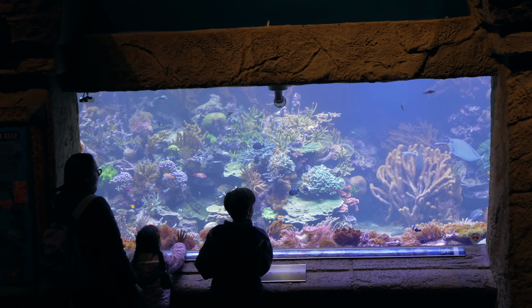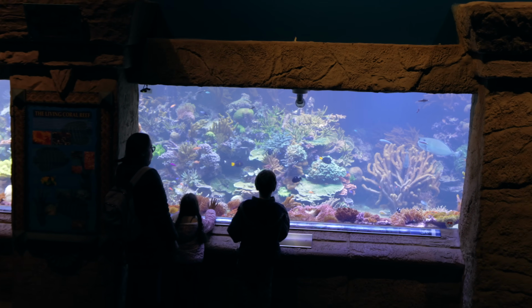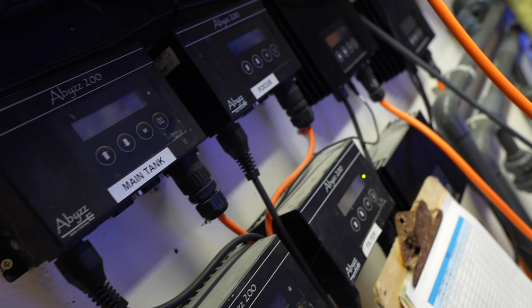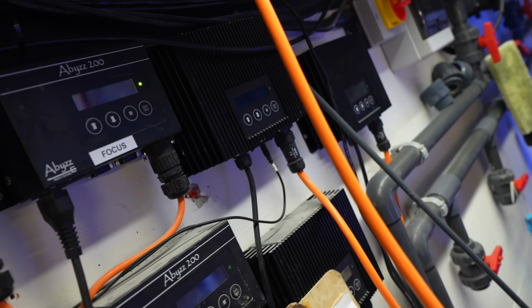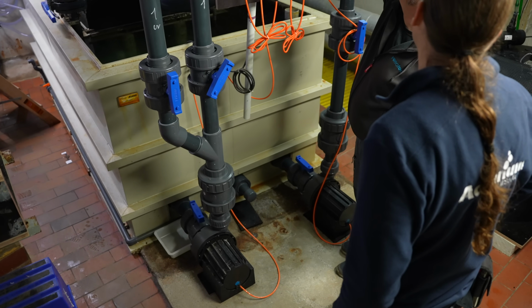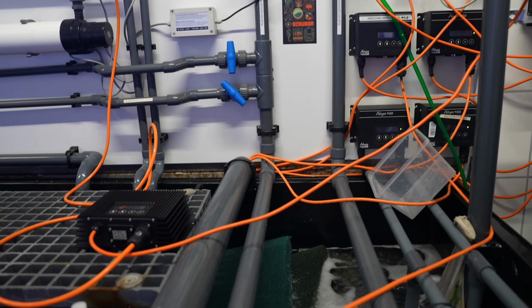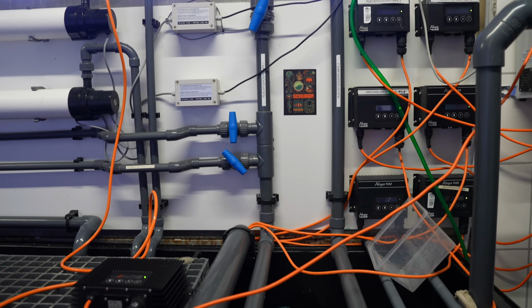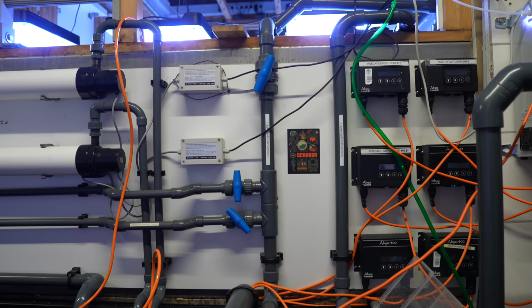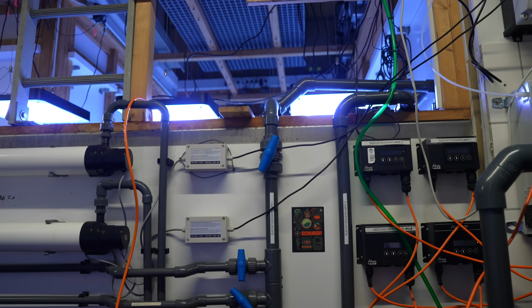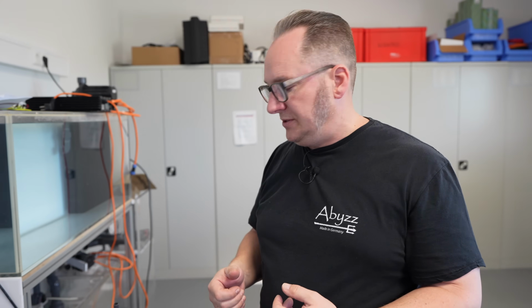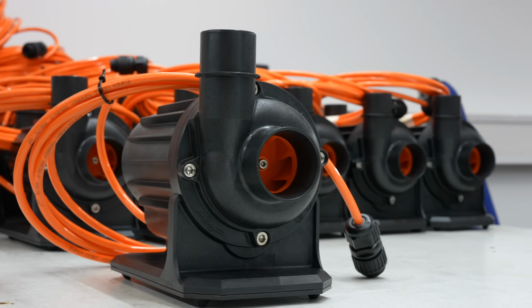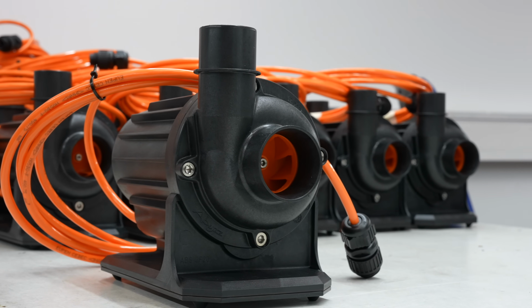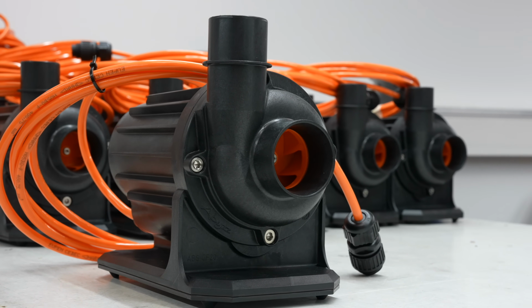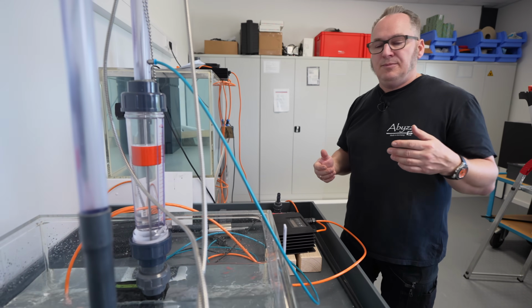And you can imagine, like in a public aquarium, for example, right now we're talking about 30 watts that we're using more, but they have 200 pumps behind the scenes. And we're not talking about only those giant pumps, because all the engineers and tank designers usually take precautions in doing the right plumbing. Not always ideal, sometimes it's cost limited as well, so there are other factors that go into that, but nobody really cares about all the small pumps. So usually behind the scenes you'll see, I don't know, 100, 200 systems with smaller pumps in there, and if every one of those pumps is using 30 watts more, then it already becomes significant. For you at home, 30 watts is not a huge saving, but if you have an A400 or a 750 watt pump running your pond, that's when it becomes really relevant, because then you're very easily at a couple of €100 or $100 per year that you're saving.